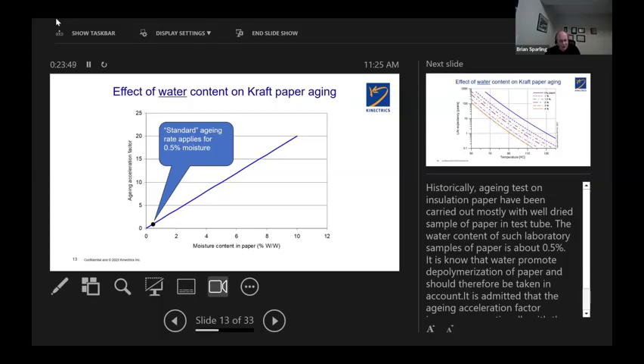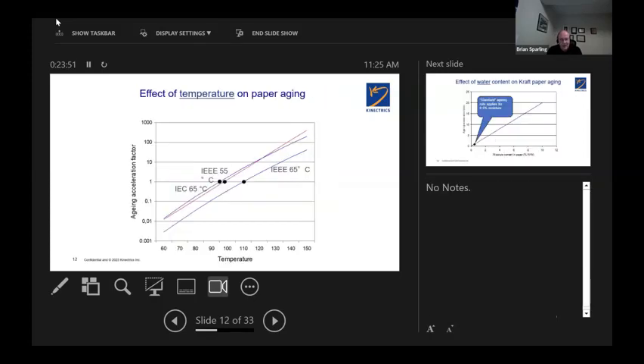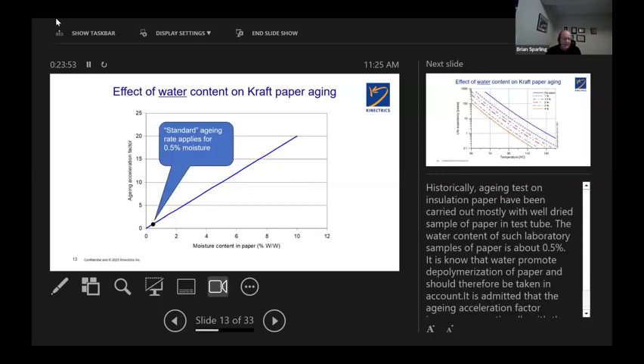So when you put the two together, temperature and moisture, you can see now that the two have an impact that accumulates or speeds up the aging rate of the transformer, aging rate of the solid insulation. That's why we have to have a very good idea of the water content in the paper.